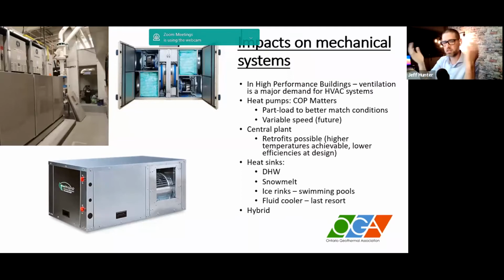Thinking differently about geothermal systems means asking what other heat sources and sinks we can combine to help balance our ground loop system. With cooling dominant applications, we want to look at heat sinks where we can reject heat to avoid rejecting too much to the loop. Domestic hot water comes up as an immediate option - if there's a building with a fairly large domestic hot water load, we can use that to dump into.